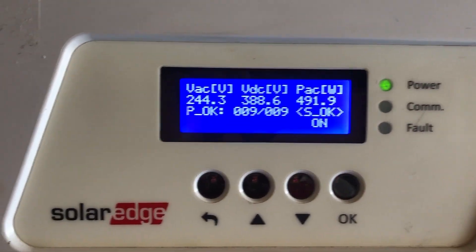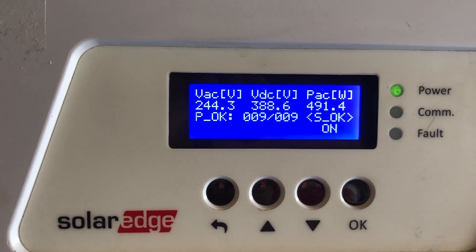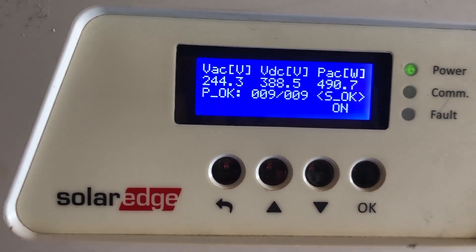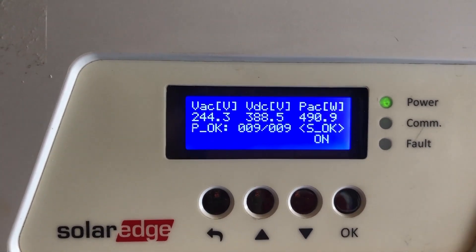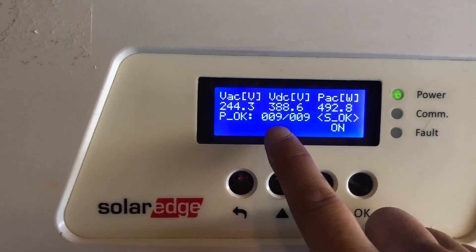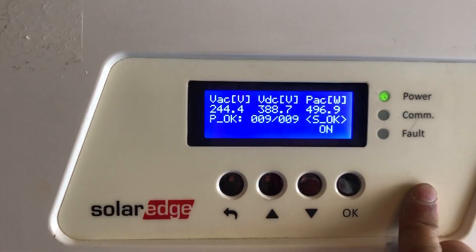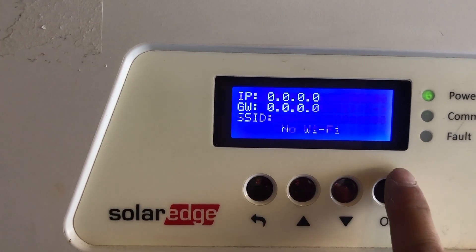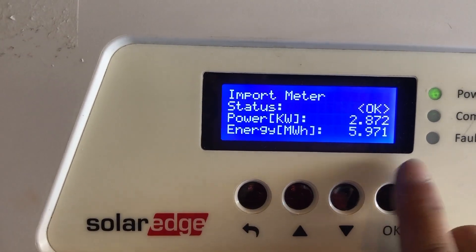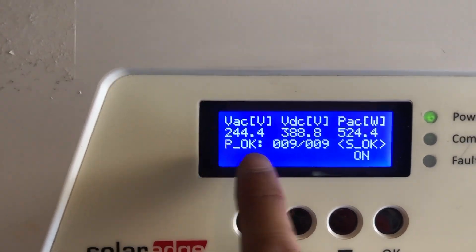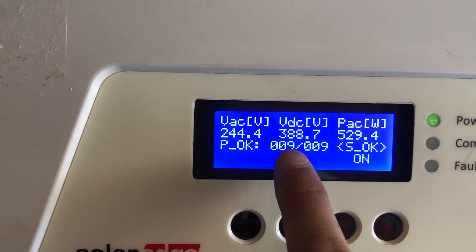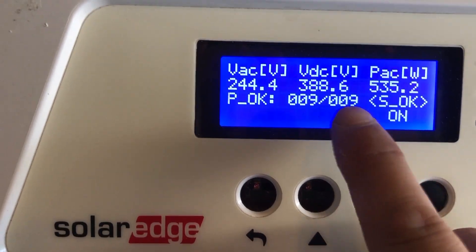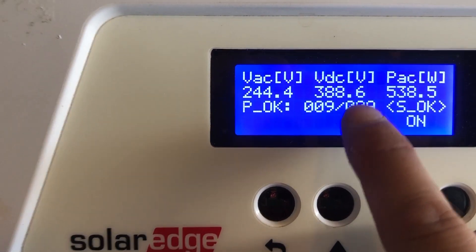In this video I want to show you how to troubleshoot a missing optimizer in your string that is not showing up. In the SolarEdge inverter, once you activate the status screen, here it says P — that means how many power optimizers. Nine out of nine is what is showing here, and I'm supposed to have ten, so one of my optimizers is not showing up.